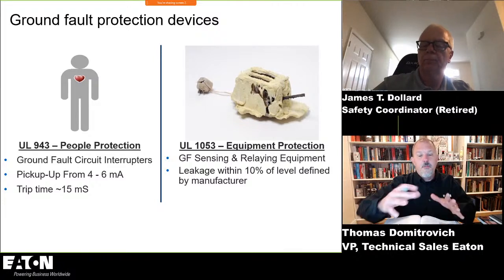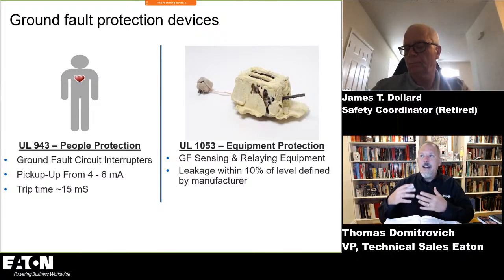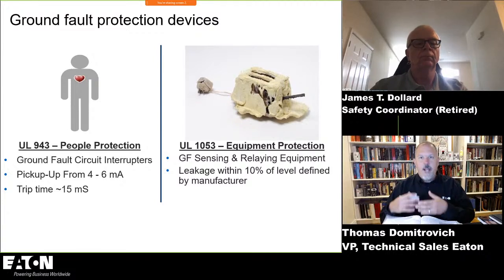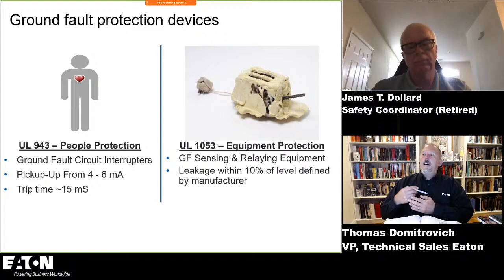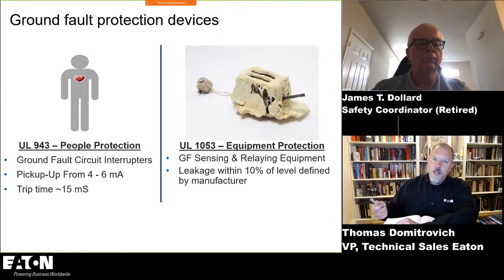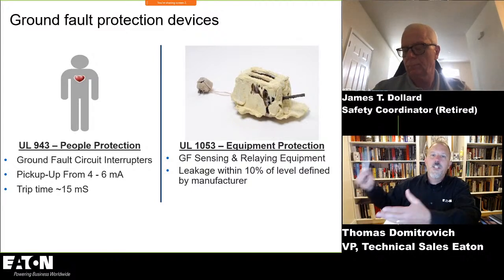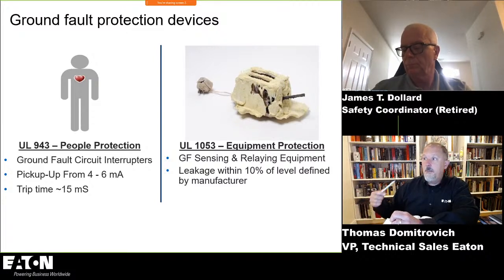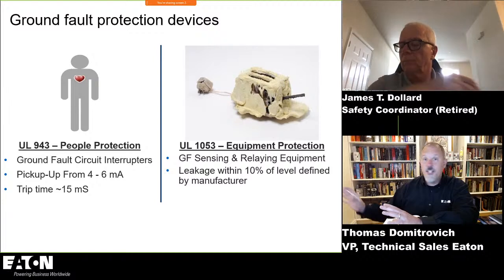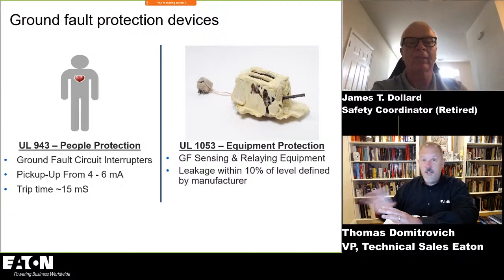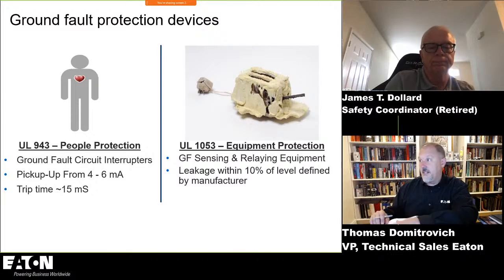And then I threw this in there. Every time I do an education around ground faults and shock protection, I know people use terminology freely, and sometimes we'll say ground fault. I've heard GFCIs referenced as GFP, right? But there is a distinct difference between ground fault protection of equipment and ground fault circuit interrupters in the National Electrical Code. I just try to drive that home to raise the awareness that a GFCI is not a GFPE device, and GFPE is definitely not going to provide the same level of protection as a GFCI device.